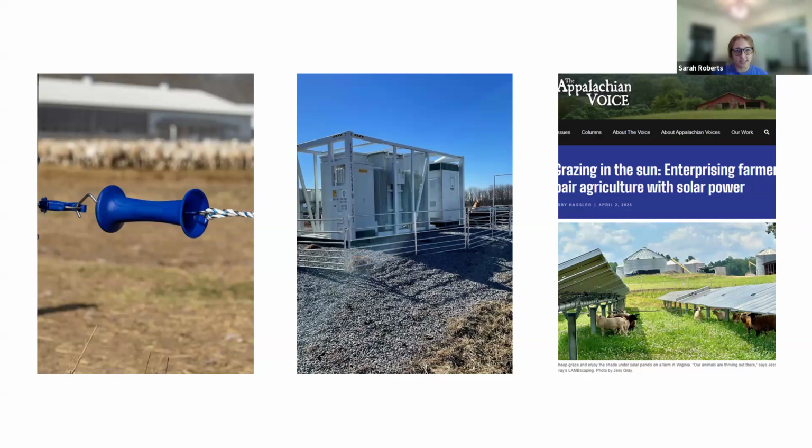And then with our grazing vendors, both our third party and our self-perform vendors, we're still figuring out the best way to do things because we're just now getting to a point where we are considering these challenges up front and in the design stages. Whereas a lot of our sites were designed with land management in mind, but not necessarily having animals on site as well, for instance when we were doing fencing and protection around the string inverters and central inverters. I'm sure Terry sees it a lot, as well as Jesse. If there is not fencing around inverters, the sheep are just drawn to them. They have shade, and they just want to be there next to the inverters.